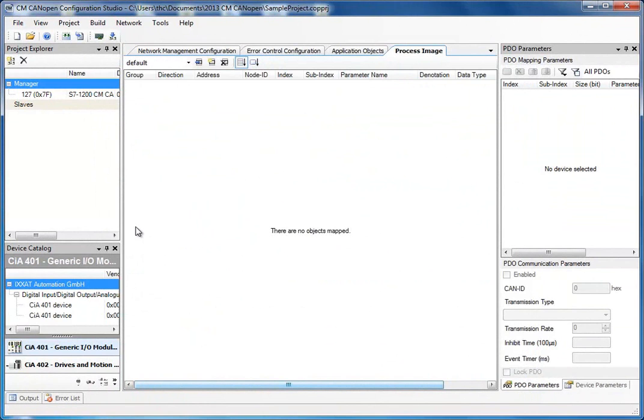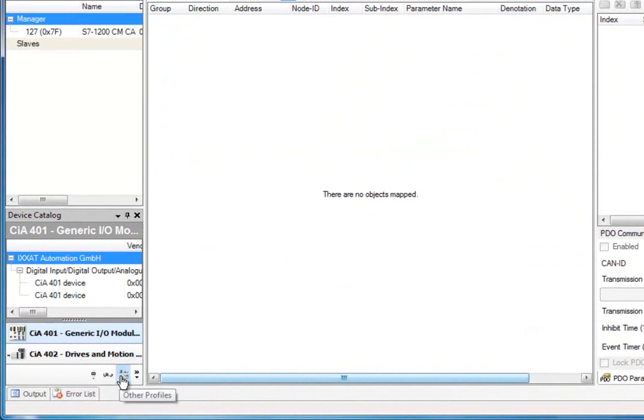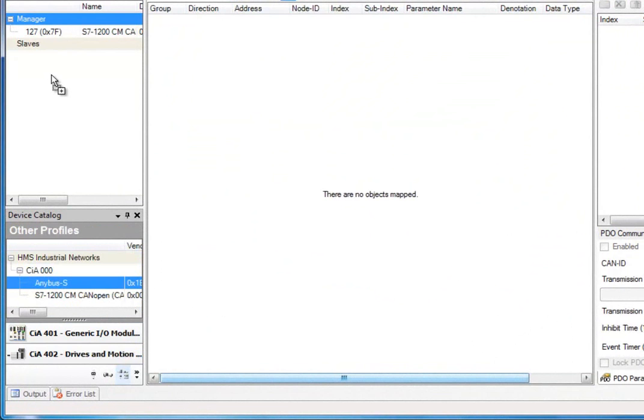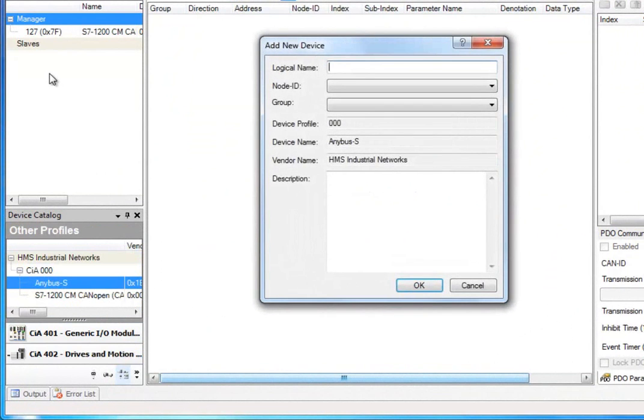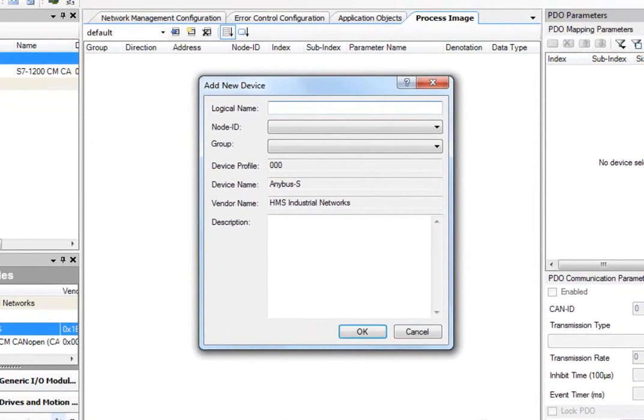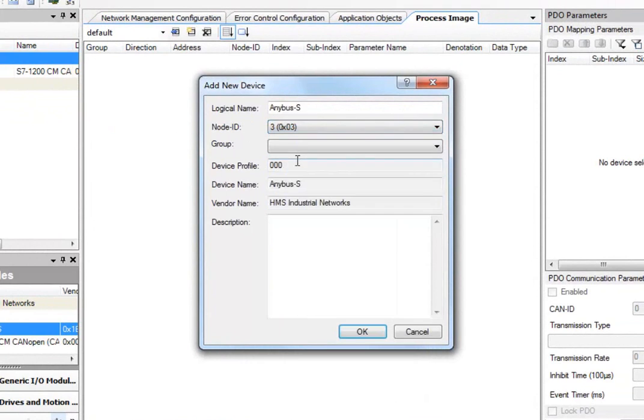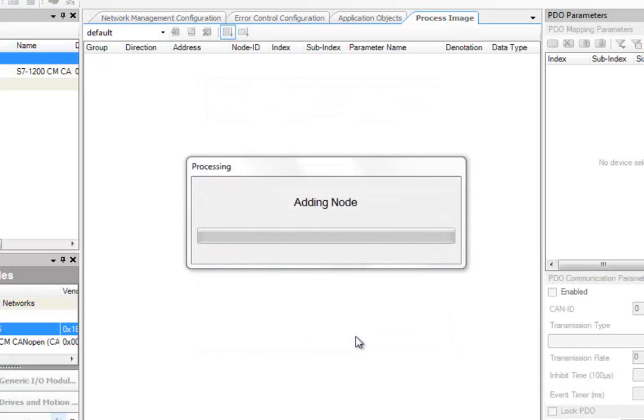I close this window and then move on to add this as a slave. Since the Anybus S does not have a device profile, I go to the tab for Other Profiles, which I find here at the bottom of my window. I can now simply drag the device to the Project Explorer window and drop it here. I now need to specify a name for my slave, since there may be other devices using the same EDS file. I name it Anybus S. I also need to specify the node ID. I choose the node ID 3, which is specified on the switches of the Anybus S. Finally, I need to specify Group, which in this case is Slaves.